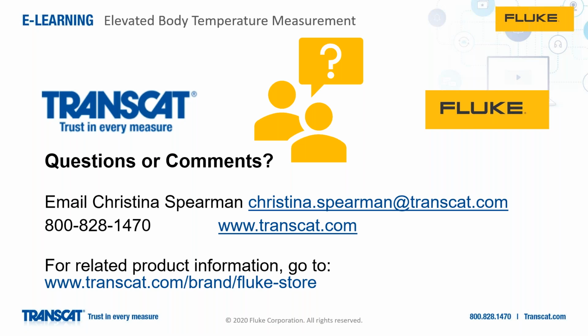We talked about all the influences on skin temperature that exist outside. So if you're doing screening before individuals come into the building, especially heading into the winter months, you'll have other influences like cold temperature outside. I'm out in Denver right now, and it's starting to get pretty chilly. If you're sitting outside for a period of time, your skin temperature will read low, and the offset within the thermometer won't be enough to compensate, so you'll get generally lower skin temperatures screening outside. Even though the product is suitable for certain outside temperatures, best practice is to always do the screening inside, and to have individuals as acclimated to the inside temperature as possible prior to screening, on the IR thermometer side.